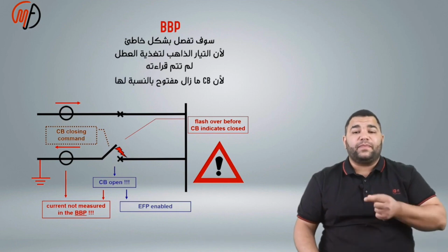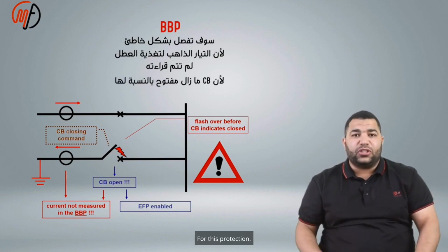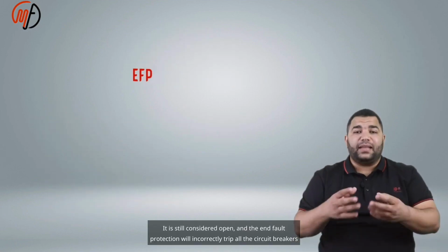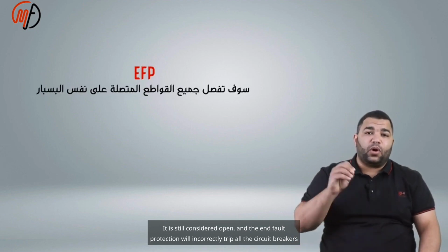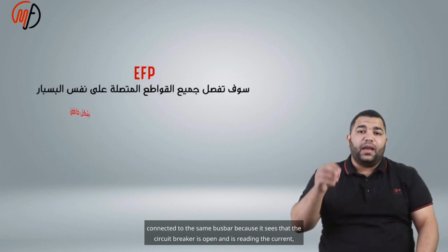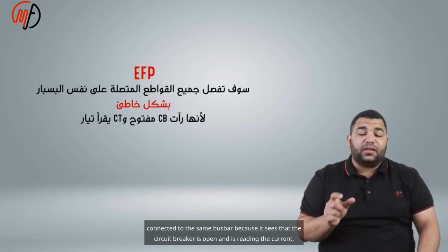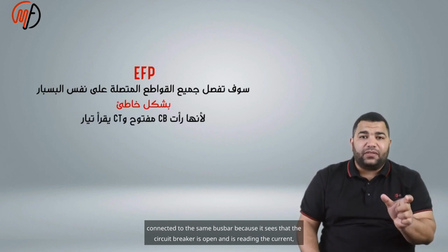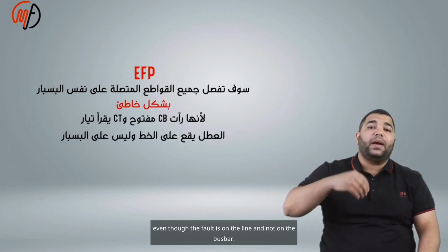This is because for this protection, it is still considered open, and the end fault protection will incorrectly trip all the circuit breakers connected to the same bus bar because it sees that the circuit breaker is open and is reading the current, even though the fault is on the line and not on the bus bar.